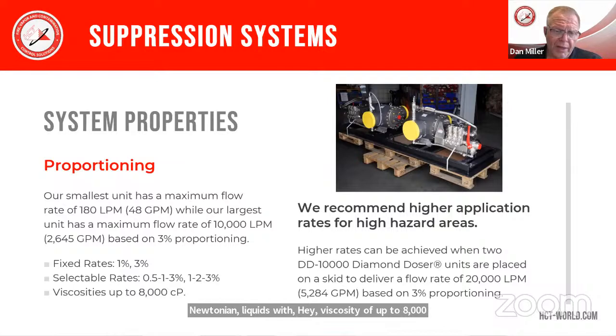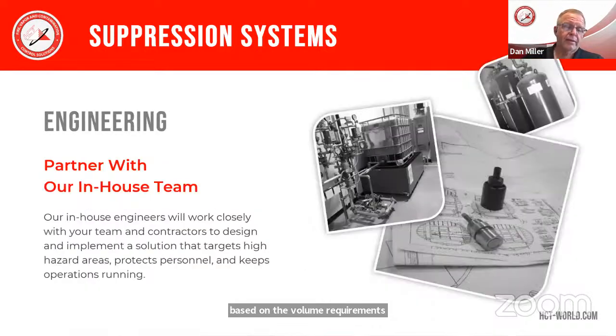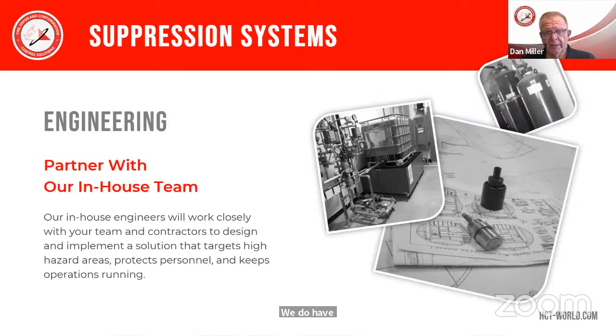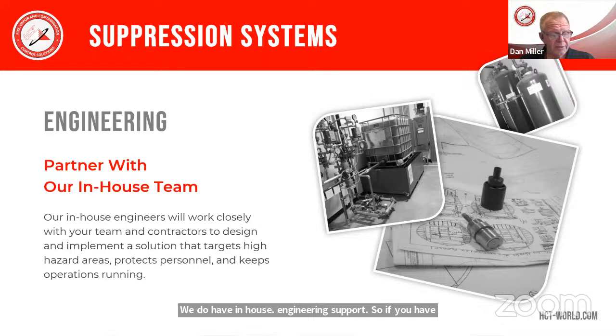So for higher application rates, as the picture shows, we can put them in tandem. So we can basically double or quadruple, whatever it takes to get up to the right rate of proportioning based on the volume requirements. We do have in-house engineering support. So if you have a fire protection system that you need us to help you design and supply, our in-house engineering support team jumps on board with you to help create a proposal, provide a complete proposal and drawings, and then once the system is installed, we provide the commissioning to put that system in service.